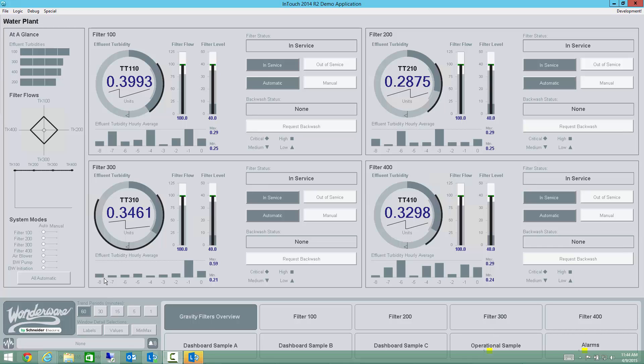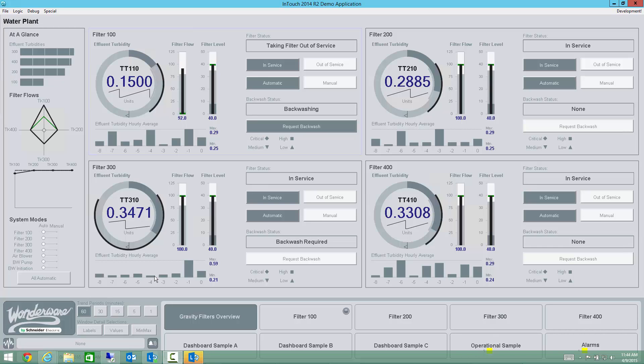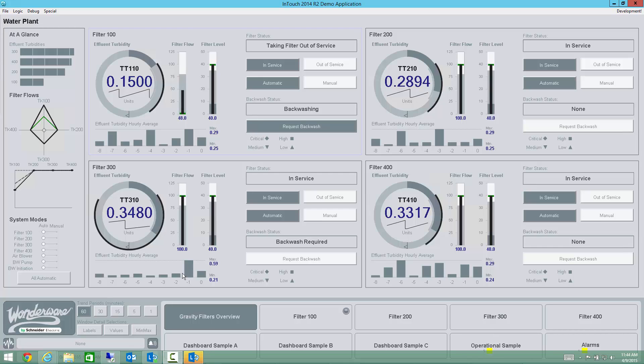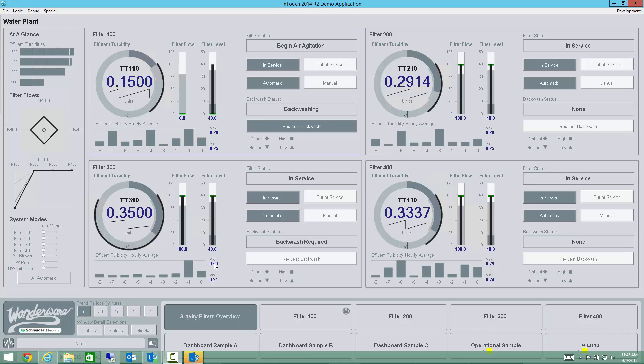To build out this particular symbol, this is utilizing the new capability with custom properties. So if you're not familiar with custom properties, those are variables that you can build in your process visualization. These variables can now be directly linked to statistical properties in your historical data. So you just go ahead and link them up directly here, and I'm telling it basically I want the average over an hour, and I'm telling it the beginning hour and the hour range and the start times here for each of these particular units. You'll notice that every once in a while it flashes because I've got this particular graphic updating once a minute, and so it does flash when it updates, and that's why you're seeing that.